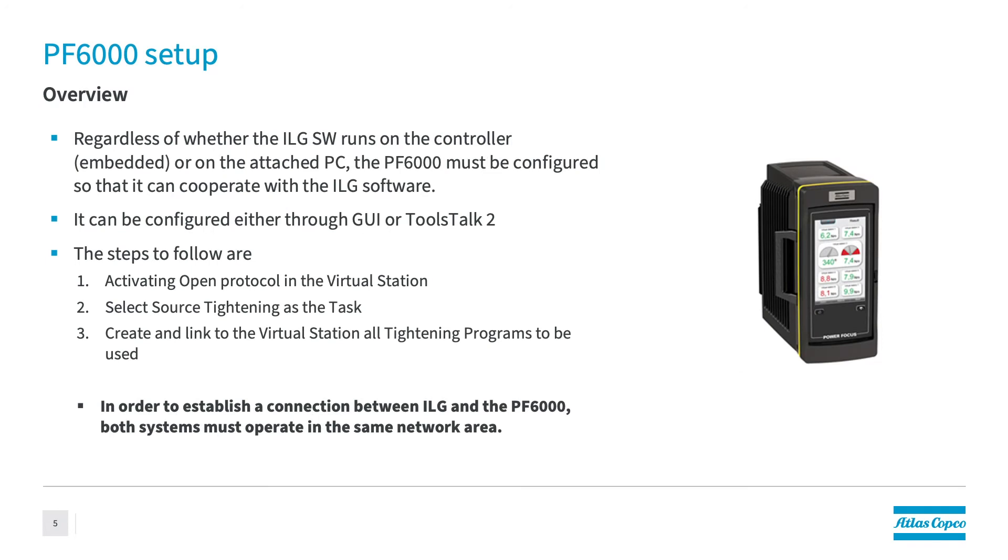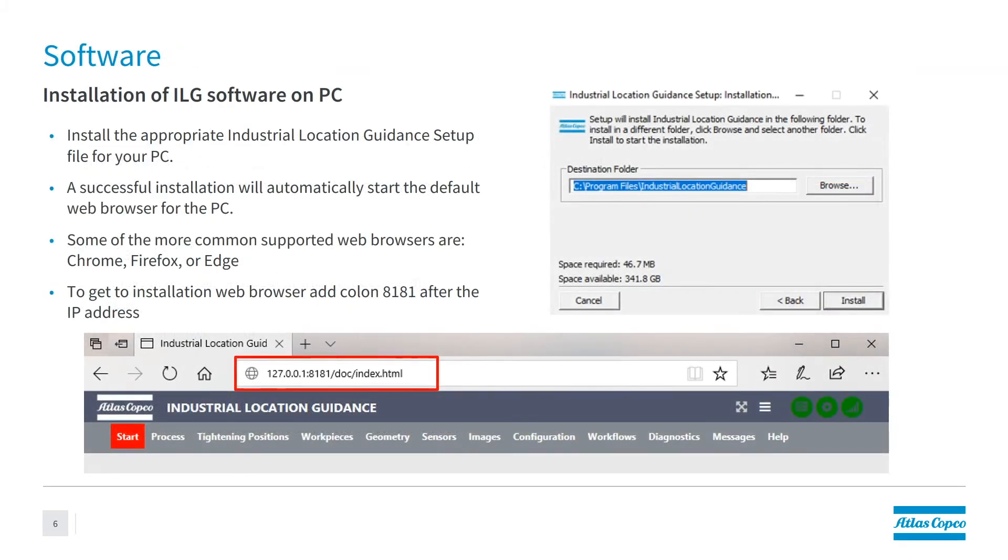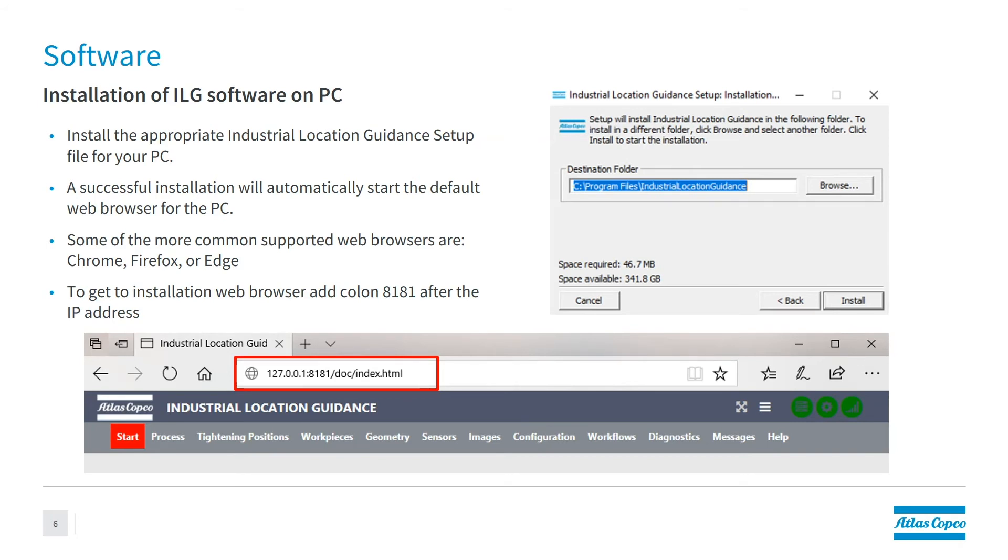Once we've completed that, we're going to move on to actually setting up the controller side of things. And you have a couple different ways of doing this. So with ILG being a system that can either run internally on the power focus 6000 system, or in the case of a power focus 4000 system, you would need an industrial computer in the station, you can run the software on that. So basically, the first step you would do is you would get the software for the ILG system, you would download it onto the industrial computer. Once that is downloaded, then you would go to the web browser, which is either Chrome, Firefox or Edge, you would type in the IP address of the system, followed by colon 8181. And this is going to give you access to the ILG software where you're going to program the actual software itself.